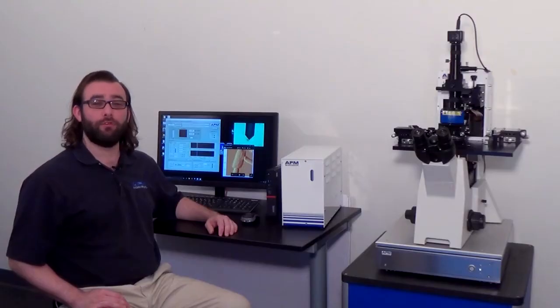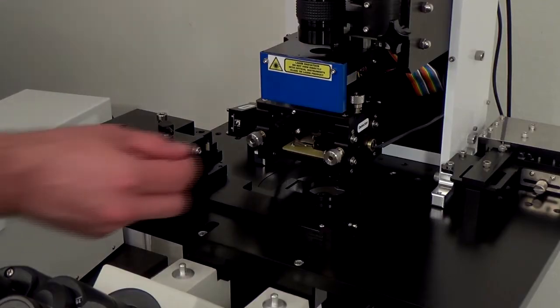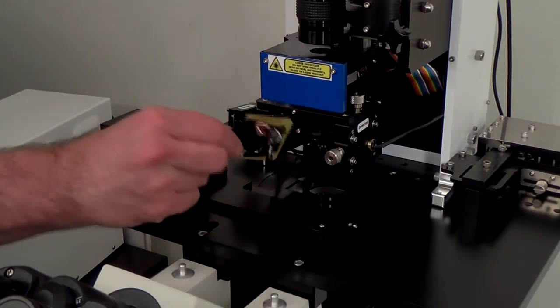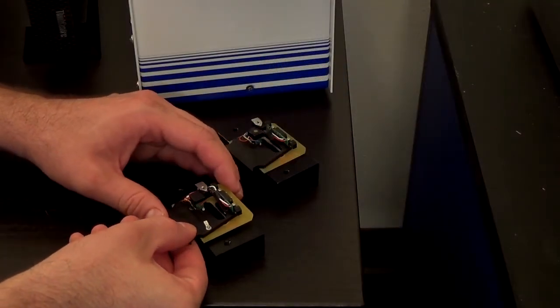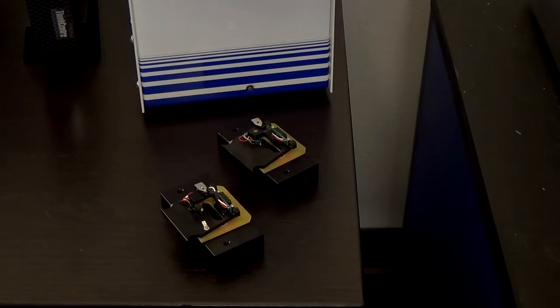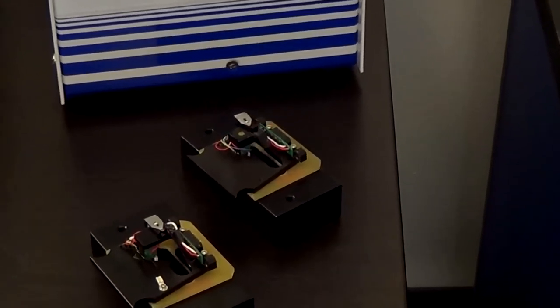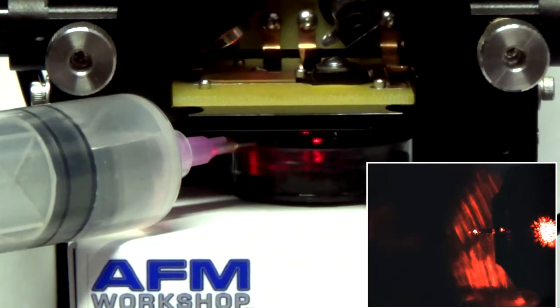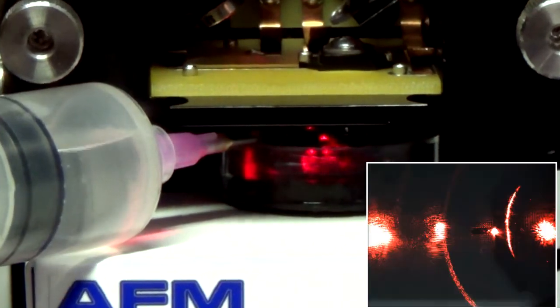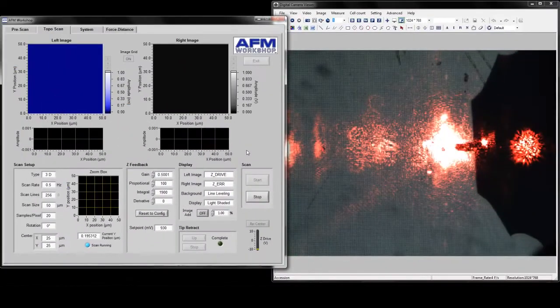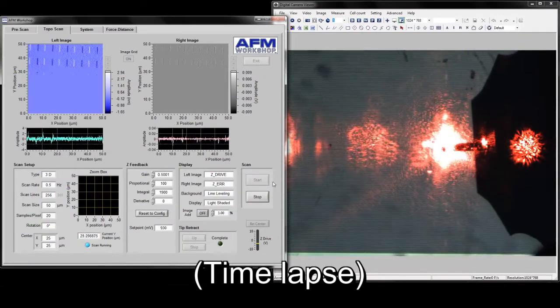There are two removable probe holders included with the LS-AFM. Probe exchange is accomplished by removing the probe holder from the light lever and setting it on a holding plate. Here, we are showing the probe holder for dry scanning. A wet scan probe holder is used for scanning samples submerged in liquids. Once the probe is inserted into the AFM, the samples submerged in liquid are imaged.